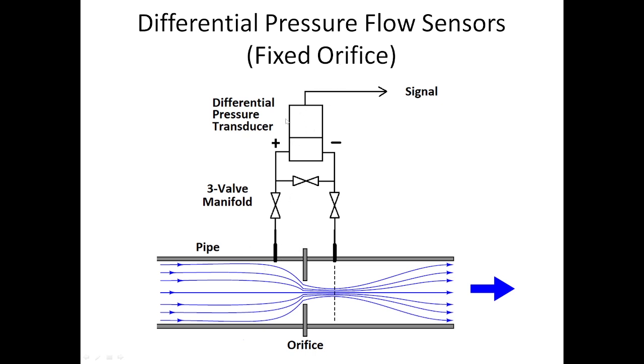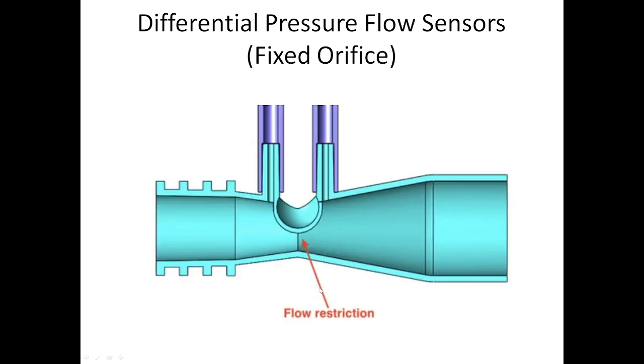So right here we have a differential pressure transducer, and it takes an analog signal, which is the pressure on each side of the orifice, and it goes up into a comparator circuit, and then it outputs a digital signal back to the computer, and the computer then comes up with whatever the calibration values are for that fixed orifice. And that gives you a pretty specific value.